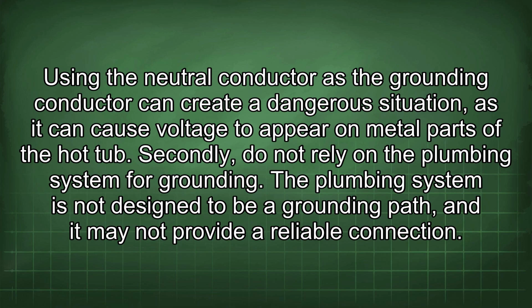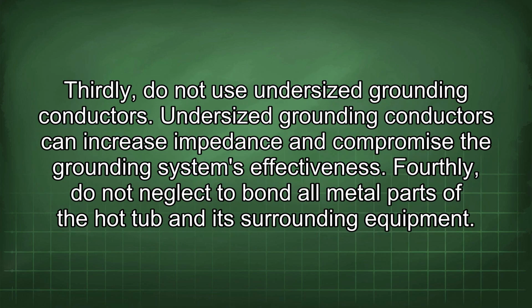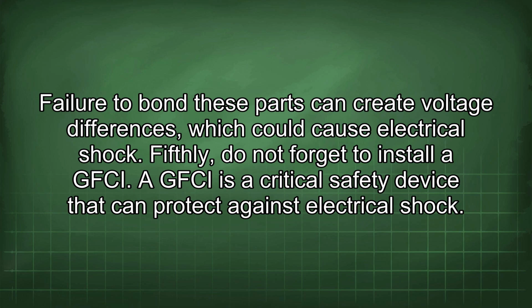Secondly, do not rely on the plumbing system for grounding. The plumbing system is not designed to be a grounding path, and it may not provide a reliable connection. Thirdly, do not use undersized grounding conductors. Undersized grounding conductors can increase impedance and compromise the grounding system's effectiveness. Fourthly, do not neglect to bond all metal parts of the hot tub and its surrounding equipment. Failure to bond these parts can create voltage differences, which could cause electrical shock. Fifthly, do not forget to install a GFCI. A GFCI is a critical safety device that can protect against electrical shock.